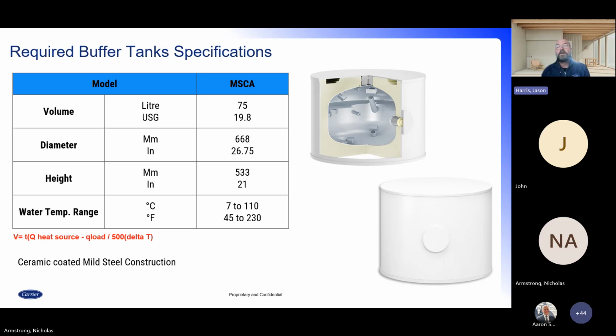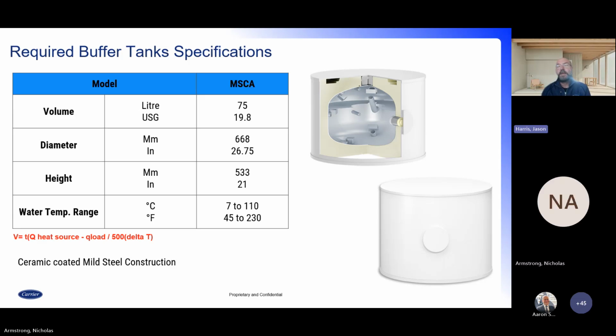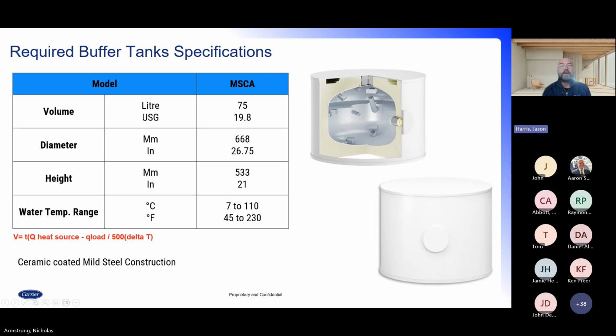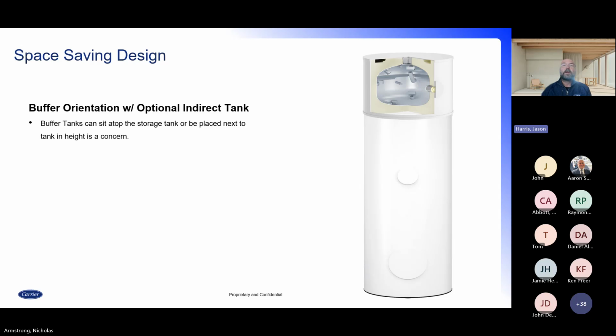Okay, here we go. So it comes with a 20-gallon buffer tank, with a temperature range from 45 to 230. And this buffer tank can easily mount on top of the domestic hot water tank. Next slide. And just as I mentioned, you can see that it saves space with a smaller footprint, but you cannot mount the tank on top of the buffer tank just because of the weight.